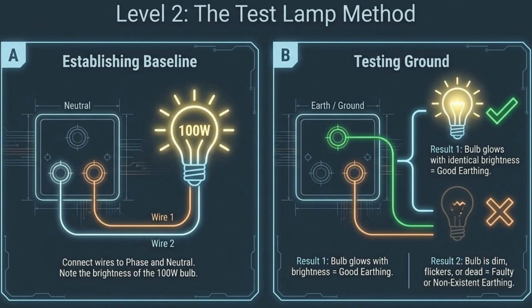For Level 2, the test lamp method, first establish a baseline by connecting a bulb to the phase and neutral ports. Then, test the earth by connecting the bulb to the phase and earth. Identical brightness confirms good earthing.